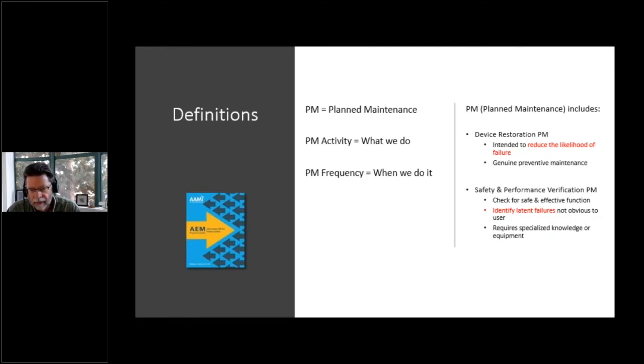Most of what we do is not really preventive in that sense. It's verifying the performance and safety. And the term that a lot of people use is finding latent failures or hidden failures. It's the kind of thing that is not obvious, but it requires people like us to come around with special knowledge and special test equipment to find a shortcoming. So the defibrillator output, the user may not know that the defibrillator output or the ESU output is lower than the setting. They may have some sense that they're having problems, but they're not able to detect that the flow rate of this infusion pump is a little bit slower than it should be. We're the only ones who can find that out. So that's another big part of PM, to look for latent failures.